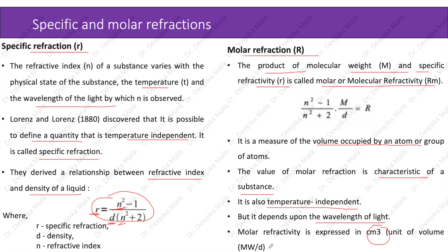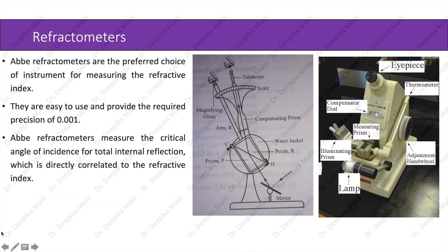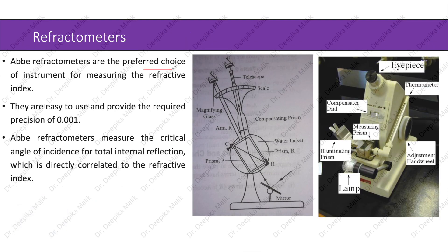Abbe refractometers are the preferred choice of instrument for measuring the refractive index. They are easy to use and provide the required precision of 0.001. Abbe refractometer measures the critical angle of incidence for total internal reflection, which is directly correlated to the refractive index.